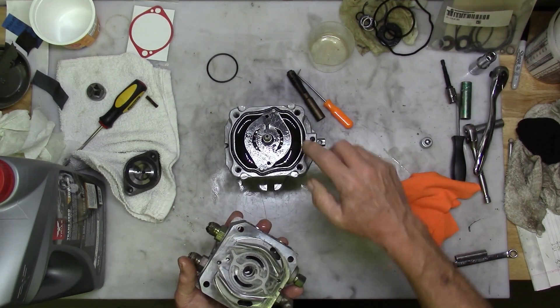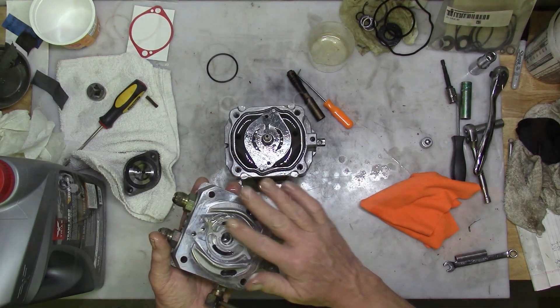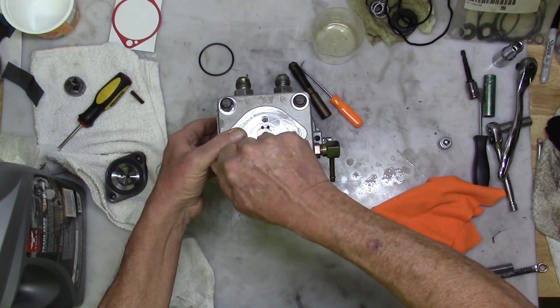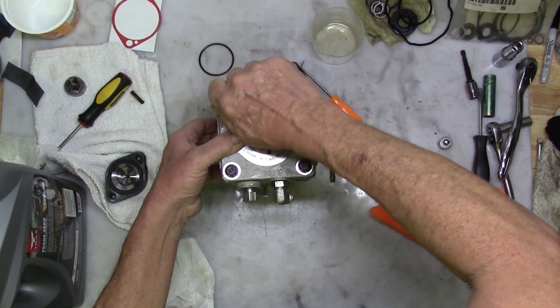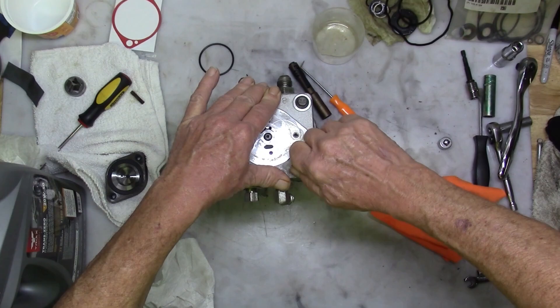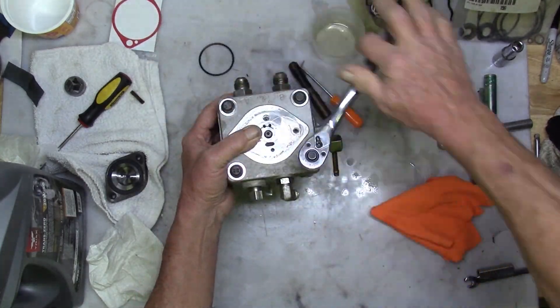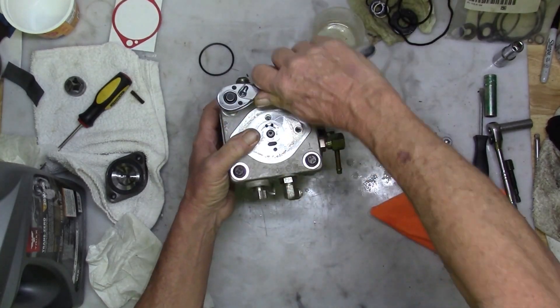Lubricate the face of the end cap or manifold and mount it to the assembly. Line up and start finger tightening the four bolts. Squeeze the two pieces together by hand while tightening the bolts as you go until it makes contact with the gasket. Once they're down snug, torque them at 180 inch pounds or 20.3 newton meters.